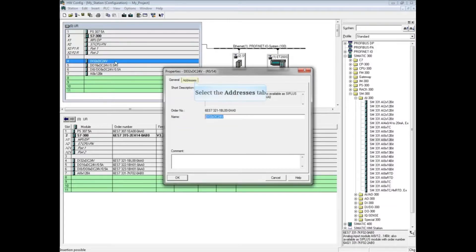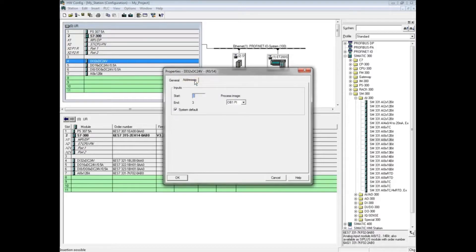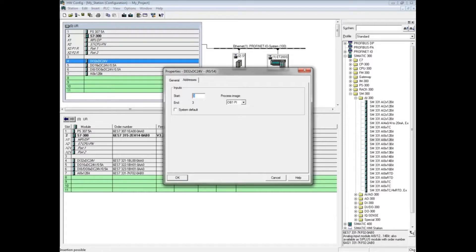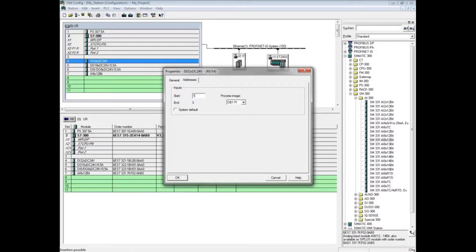Click the addresses tab to change the module's address. First, uncheck the system default checkbox. Since this is a 32-bit card, the hardware configuration editor won't let you use an address unless the next three bytes after the beginning address are free. Let's change the beginning address to 100. The module will now occupy input bytes 100, 101, 102, and 103.